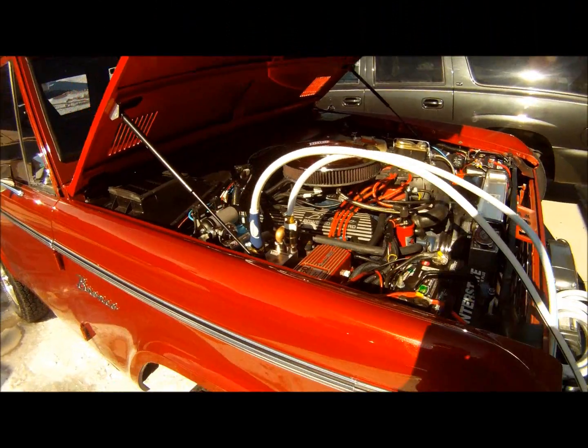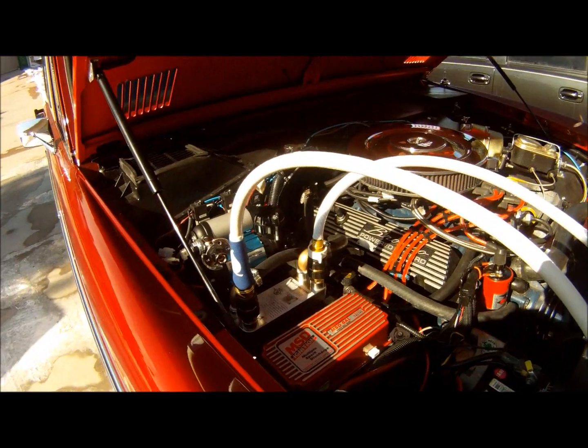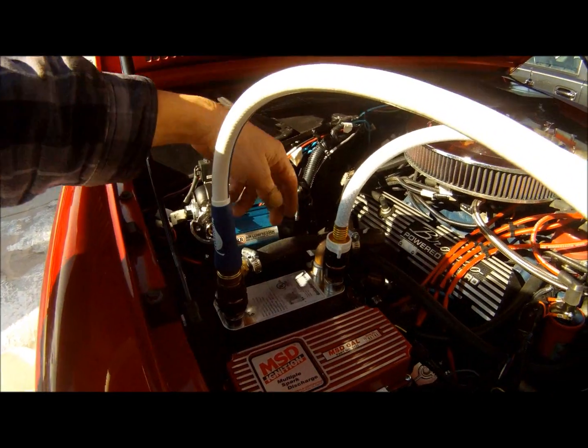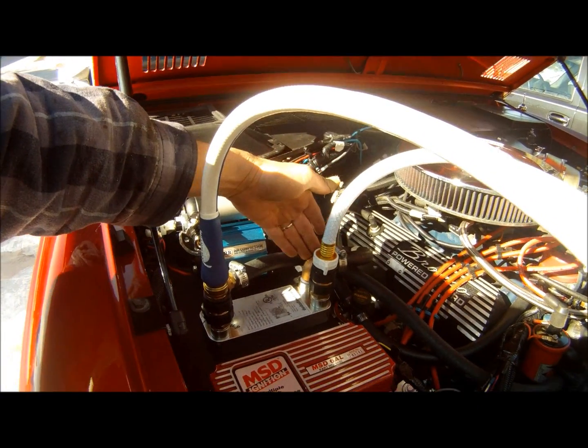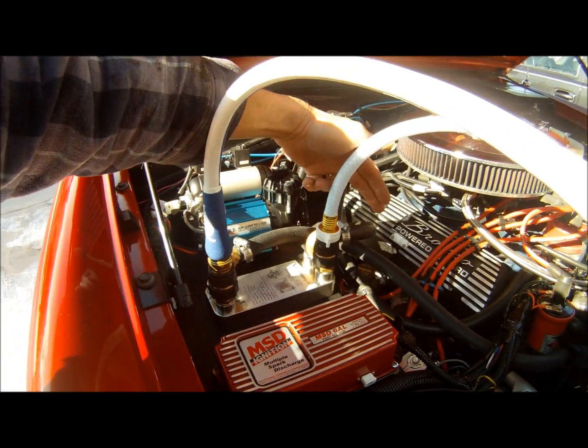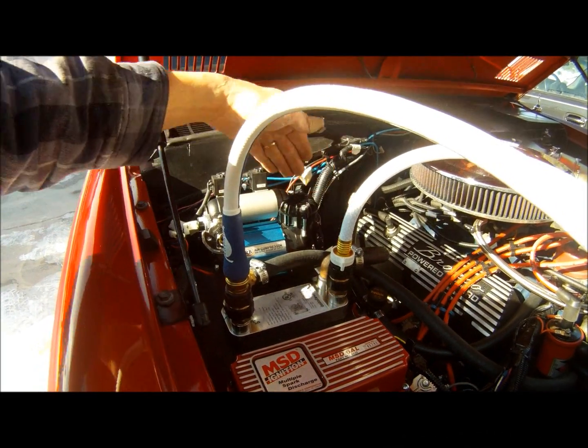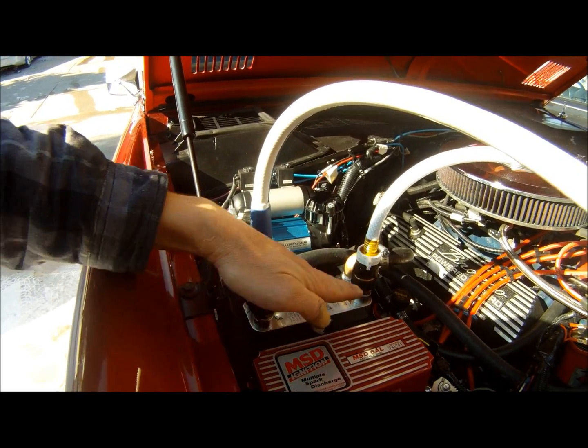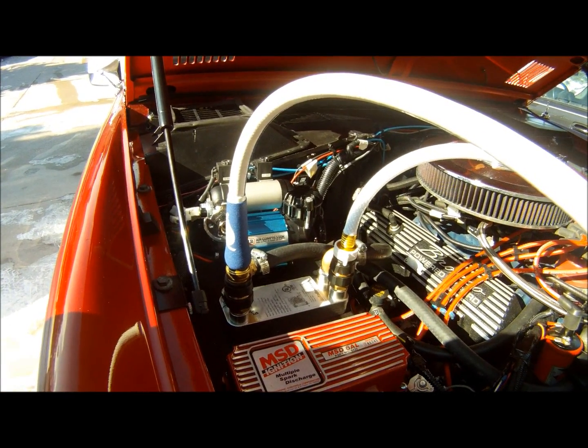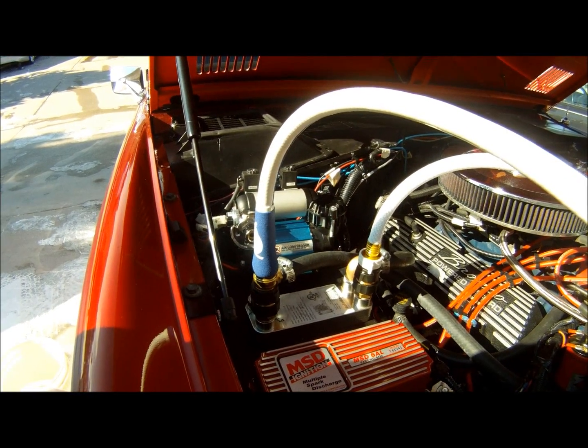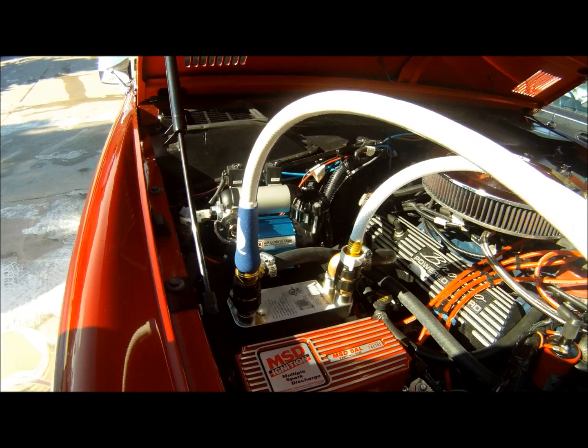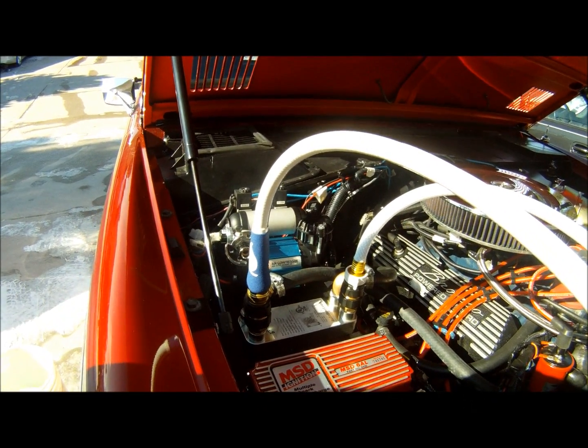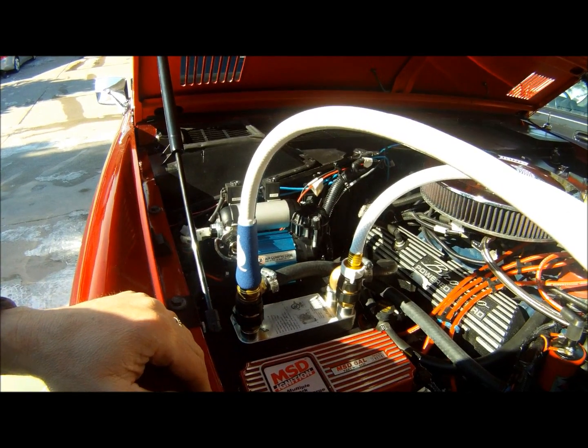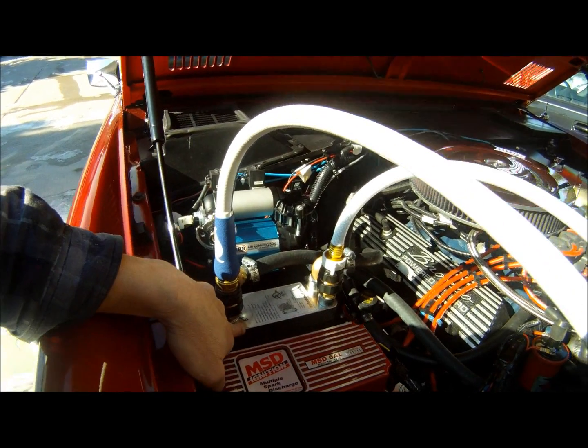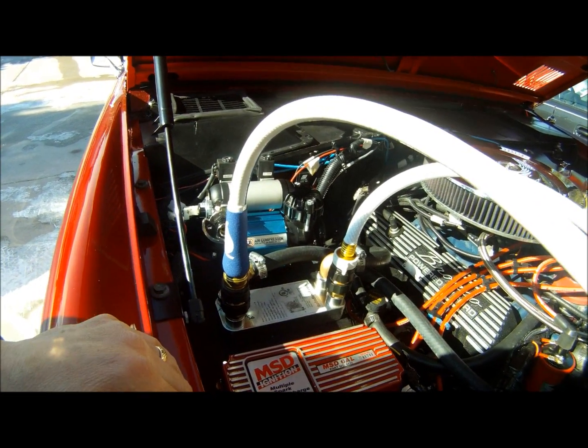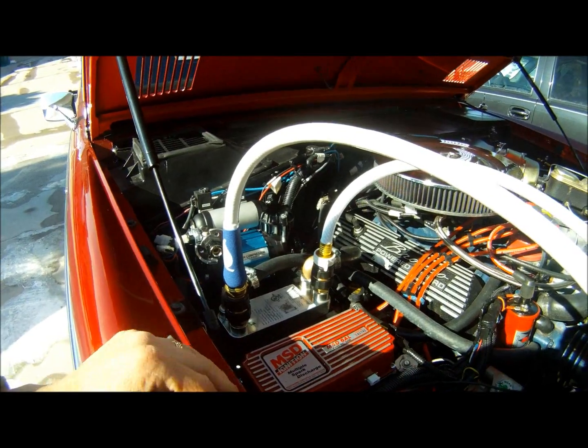One other point I wanted to make: from what I've read, on these heat exchangers you've got hot water flowing in and out. Your cold water should come in on the opposite side so they cross each other inside the heat exchanger, making the heating more effective and quicker. Your flow should go against the direction your hot water is coming in. I did mark it cold here, so we'll remember, but you never know.